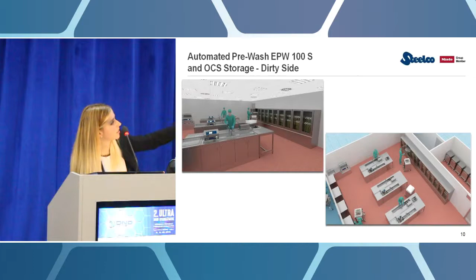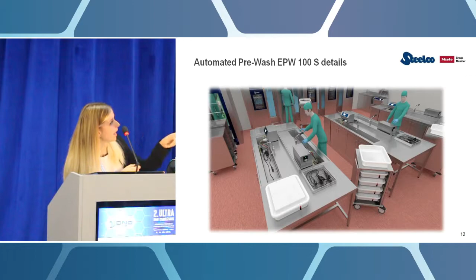We decided to offer these specific sinks because when doing the leak test, if the endoscope is coiled too much and if the leakage is minimum, then you risk not to see it. So this way you will be able to lie the scope in all its length into the sink. Then you have pass-through endoscope washers.